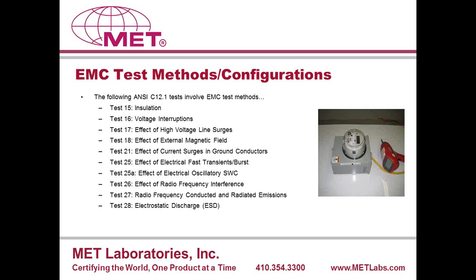And then the electromagnetic energy, which is created from that impulse, we are subjecting the meter to that electromagnetic energy and observing it for any failures. Typically what we see during this test is either the meter will be okay, sometimes the display will go out, or we might have component damage as a result of this test. But this test is only required for self-contained meters. So if you have a product that is not self-contained, meaning you're using external current transducers, then you're not required to go through this test.